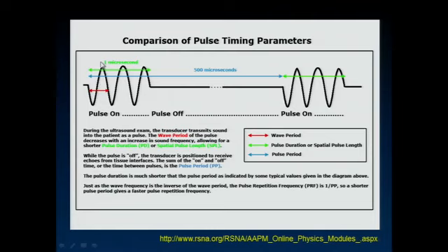And remember, we send out more than just one wavelength, more than just one cycle, because when we're in the listening mode, we actually have to hear a cycle or 2 or 3 returning as an echo to understand that what I'm hearing is the same frequency sound being reflected back to the transducer. So we send out a few of those, typically on the order of 3 cycles of that sound.